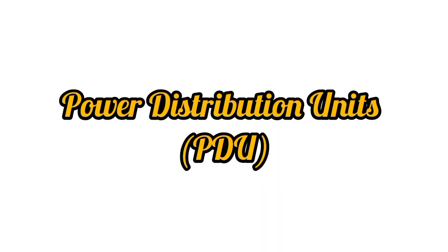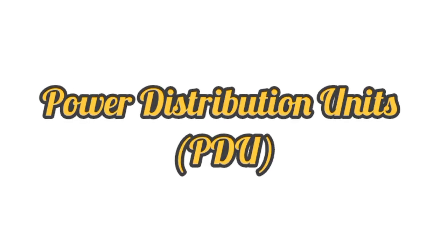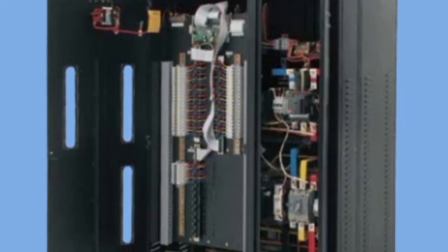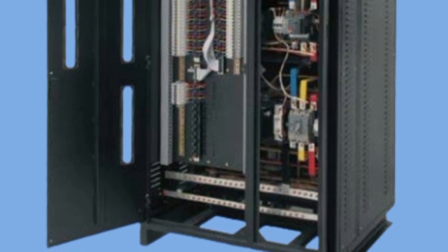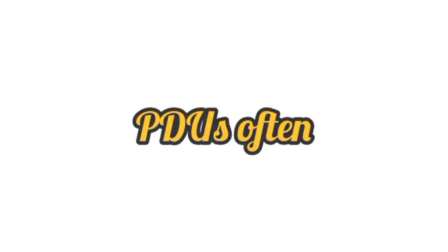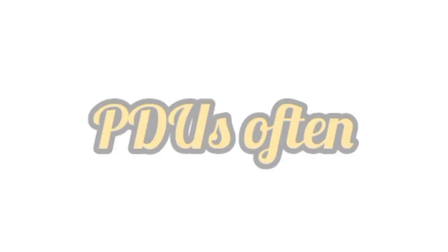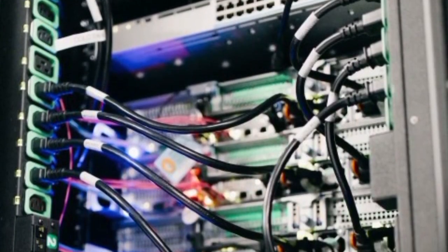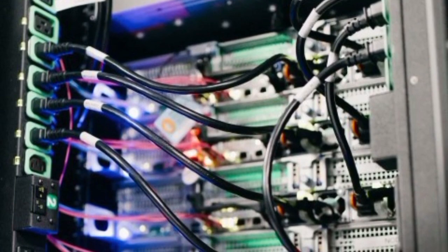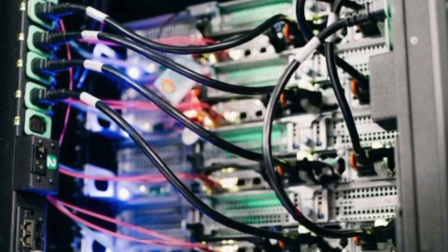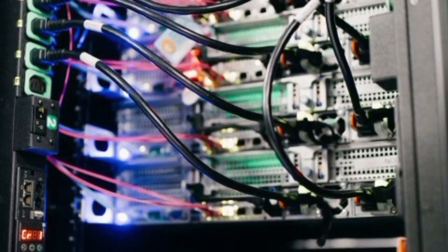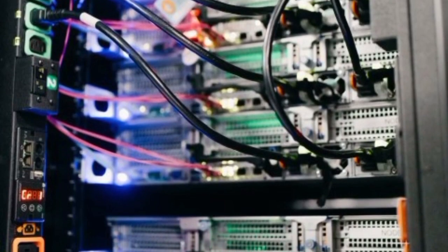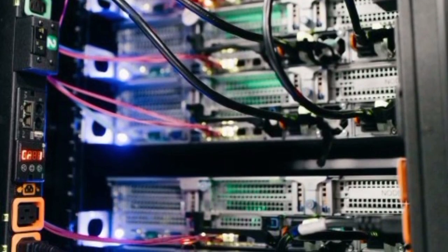Power Distribution Units, PDU. Power distribution units are typically located near the data hall. PDUs often step voltage from 480 volt down to 208 volt or 415 volt, provide branch circuit protection, monitor electrical loads, and distribute power to groups of racks.